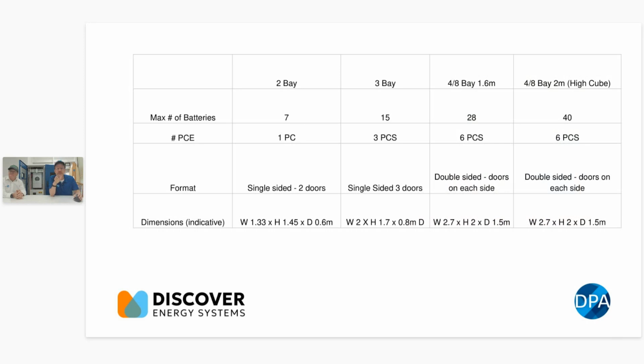There's a 1.6 meter high 8-bay and a 2 meter high 8-bay. The 2 meter high can take up to 40 batteries, and the 1.6 can take up to 28. Then I've got the number of PCE, because you've got MPPTs and inverters for each one. I put one piece for the 2-bay, but normally if it's Victron you'll have an inverter and then a 450, 100, or 200 in front of it as well, so I should have put 2 pieces really. And in the 3-bay it's going to be similar, isn't it?